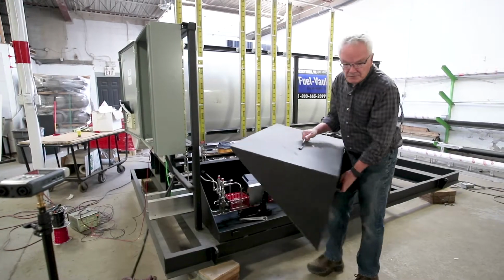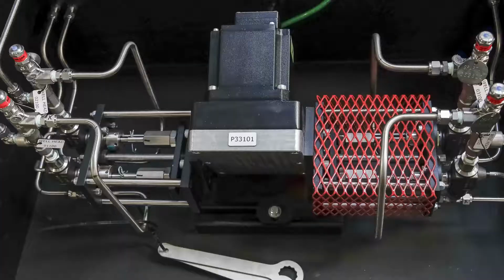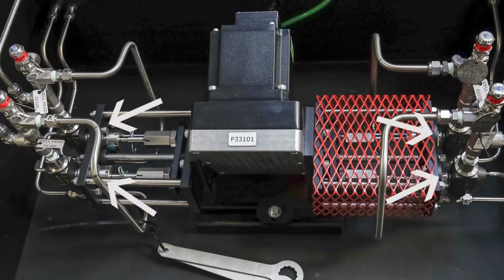At the pump skid, pull the cover off the chemical pump package and identify each of the chemical pumps, as this will be required for the spreadsheet. We are showing the pumps with numbers 1, 2, 3, and 4. Also, determine and record the piston size from each of the chemical pumps, as this will be needed for the spreadsheet.